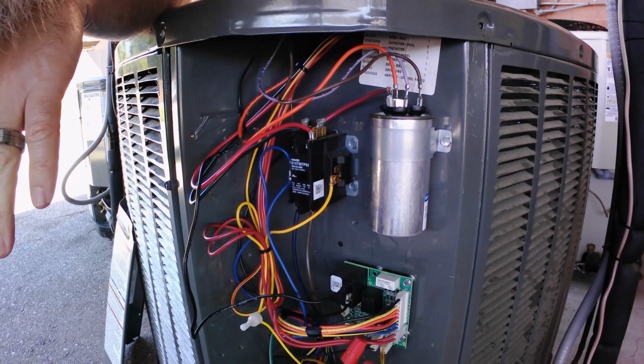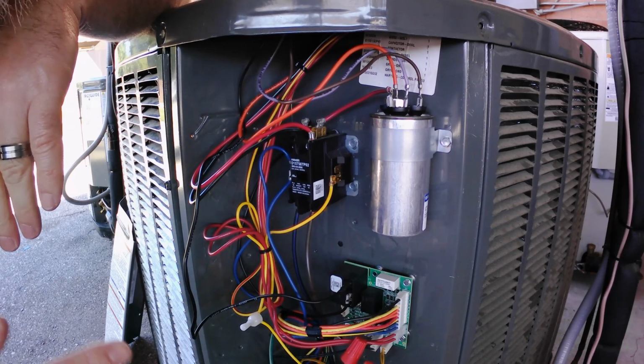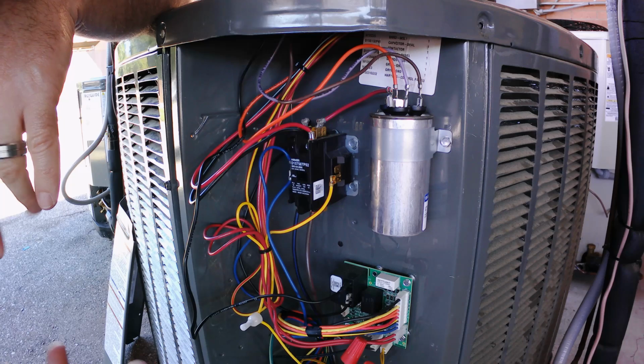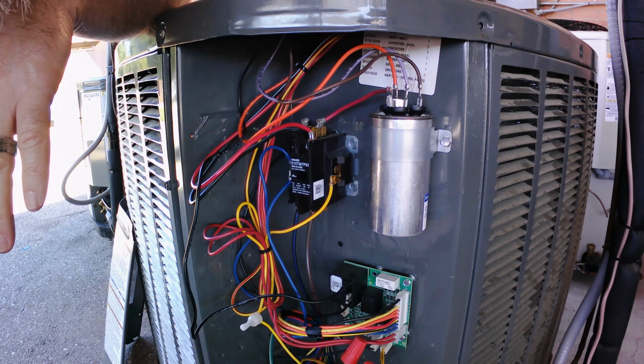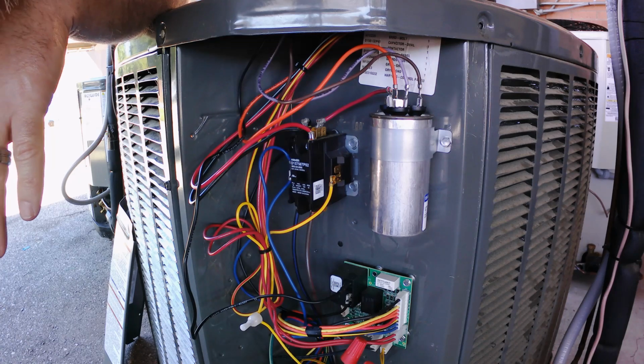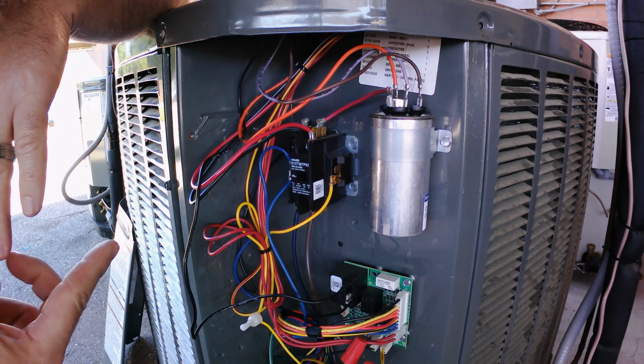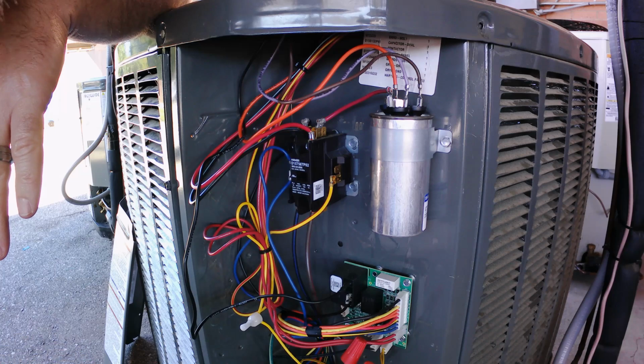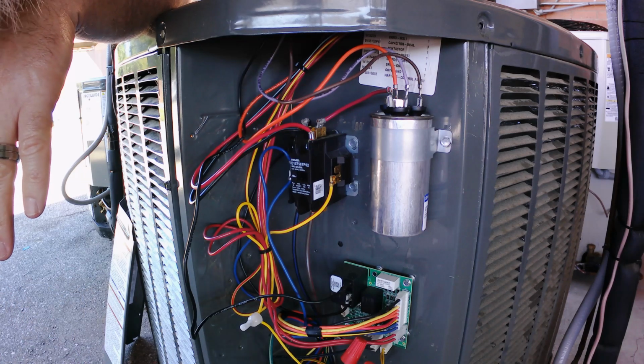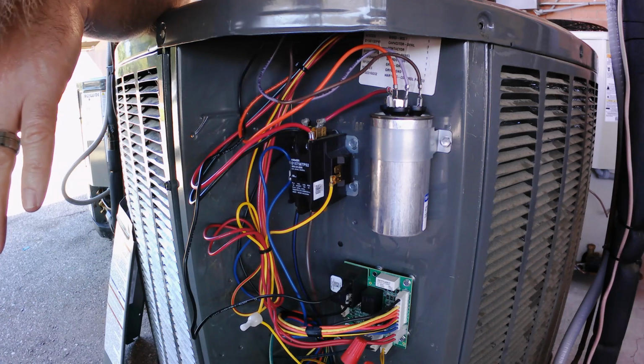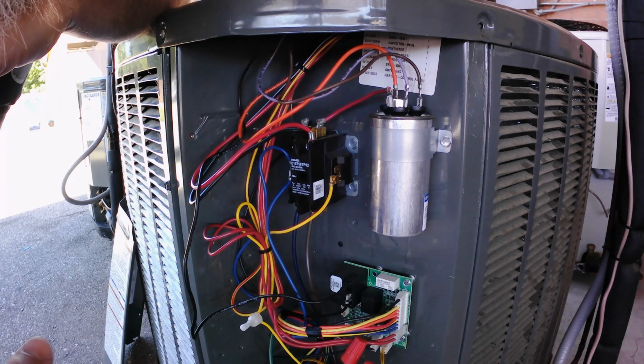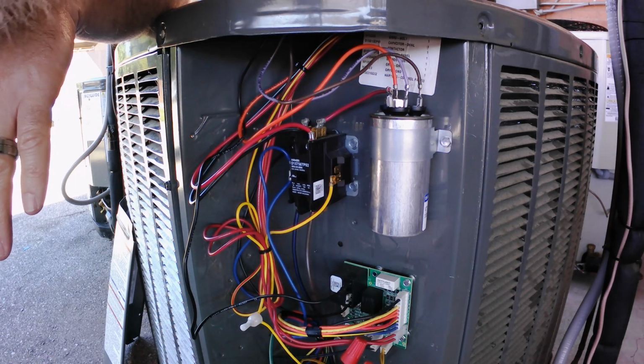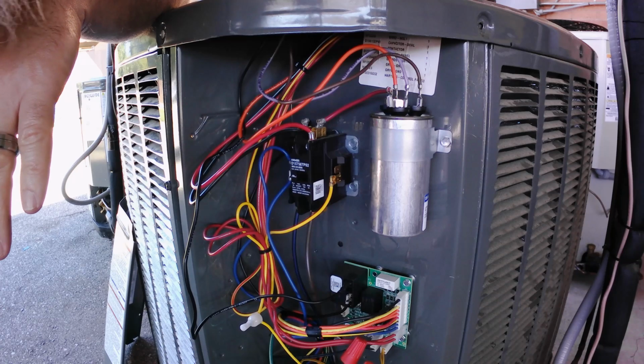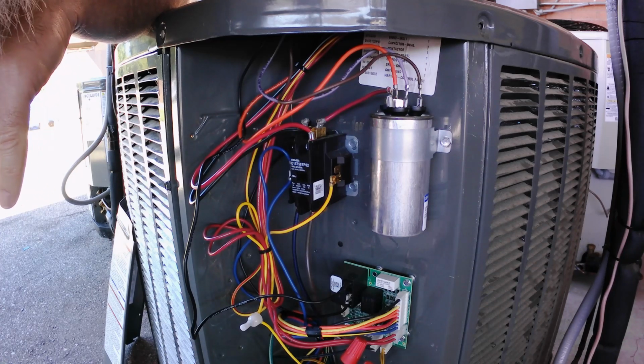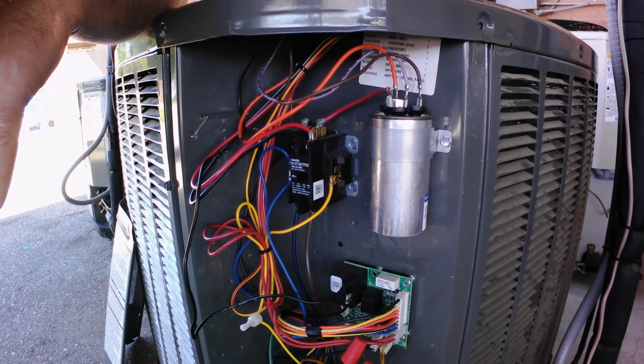So make sure you have your voltage from the thermostat. And the outdoor unit, like I said, the only thing I would really be worried about is if you have a refrigerant leak, then your low pressure switch might be open, but you would backtrack from here to find out where your voltage stopped. It's going to be some type of switch more than likely. But anyway, I hope that makes a little bit of sense. Just trying to refresh a couple people's mind to make sure that you're troubleshooting as best you can.